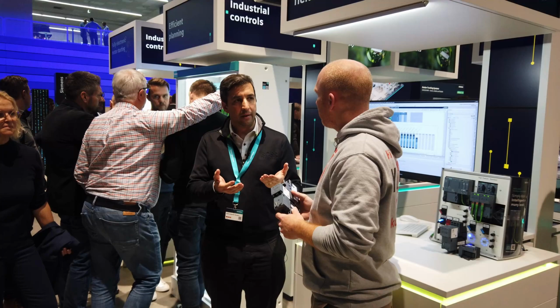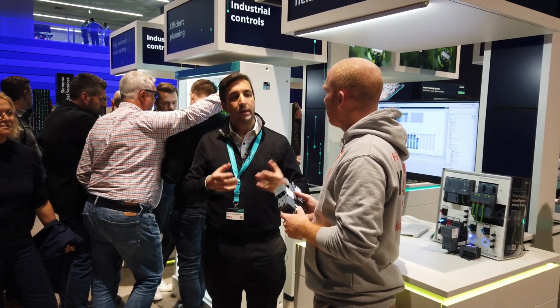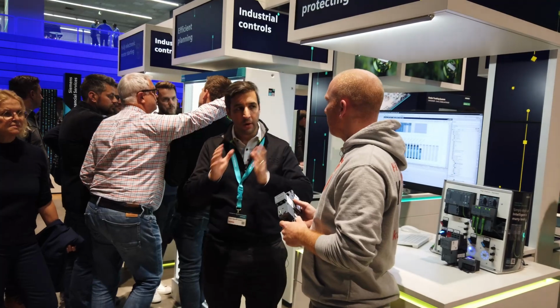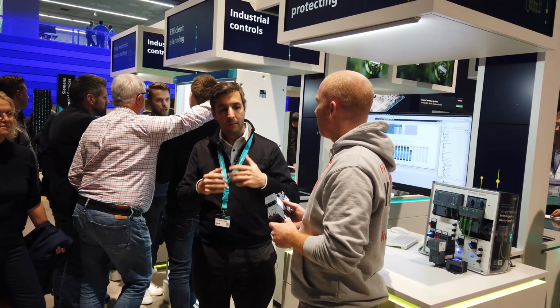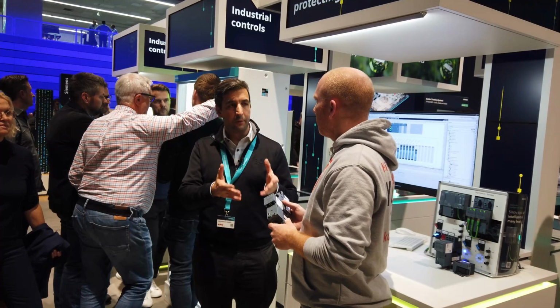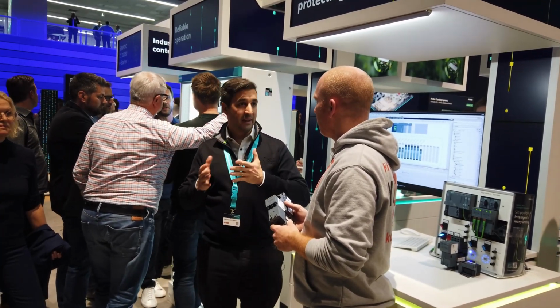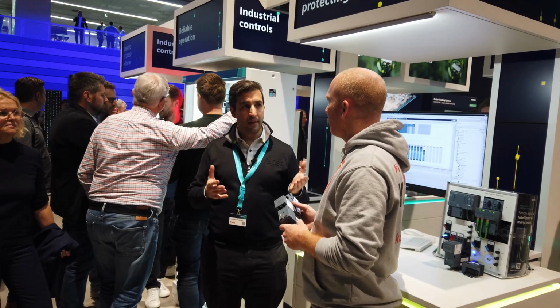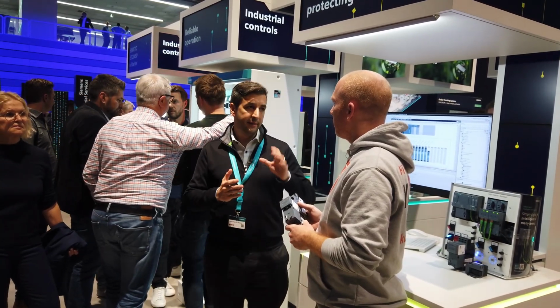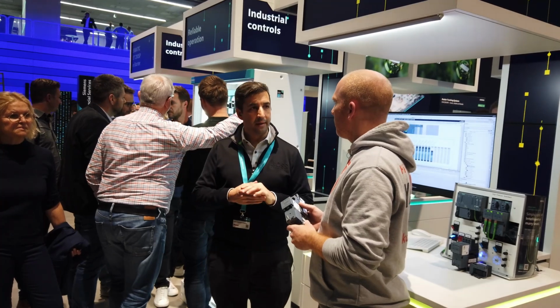Yeah, and quite nice. You can get full transparency on what's happening on your load, on your grid also, to know what's happening with the imbalance of the load, if it is too much current, too low current, too much voltage, too less voltage, or even if the contactor or circuit breaker reactions, you can know directly with this device without any special configuration on the SIMATIC side. Just by using TIA Portal, you have full diagnostic of the device and all the diagnostic is already prepared in the firmware from the PLCs, so no programming work for our customers.